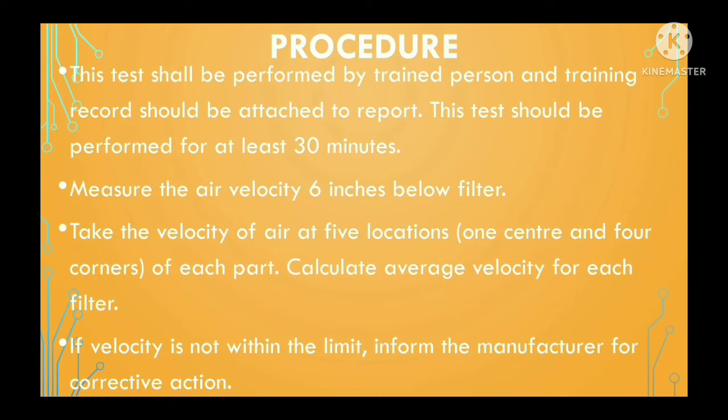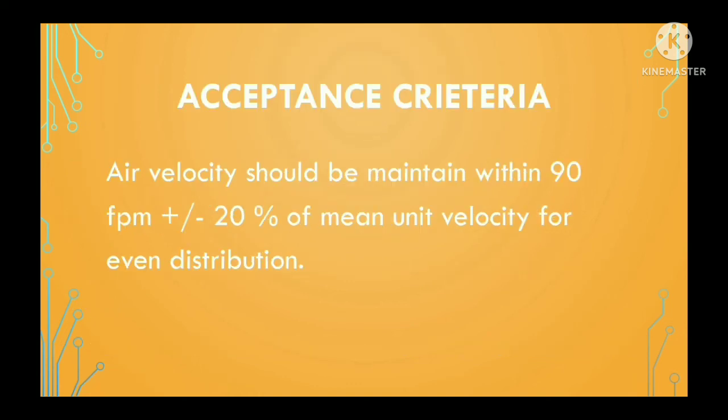Step three: take the velocity of air at five locations of each area and calculate the average velocity for each filter, in case you are calculating air velocity for more than one filter. Step four: if velocity is not within the limit, inform the manufacturer for corrective actions.